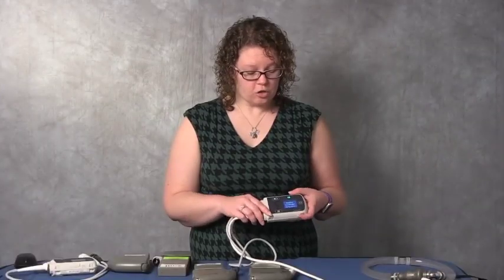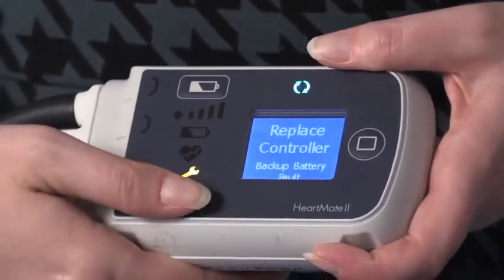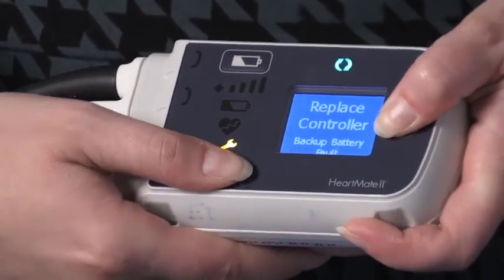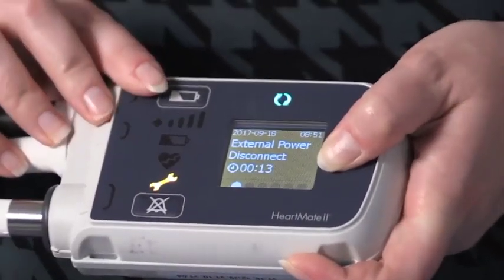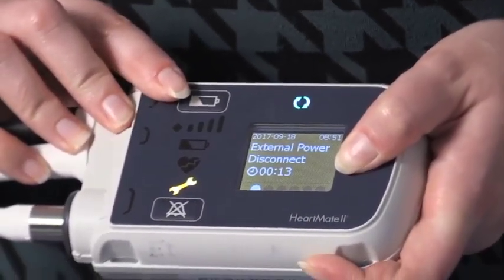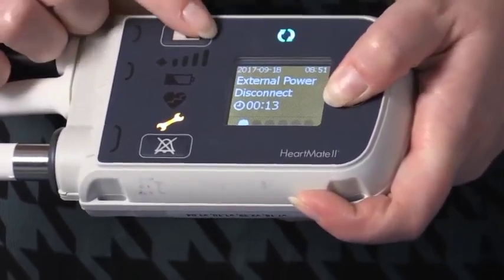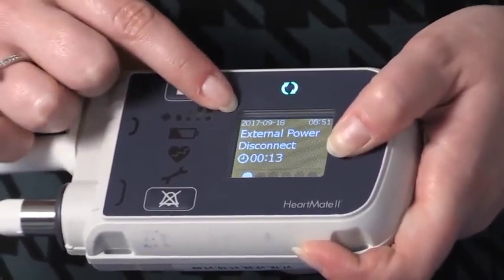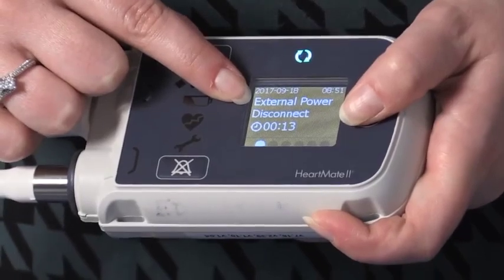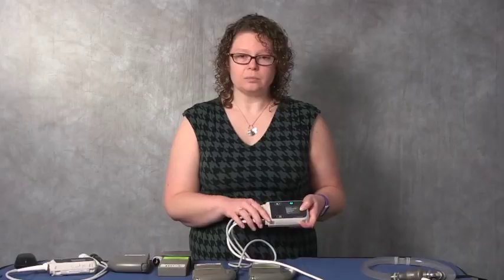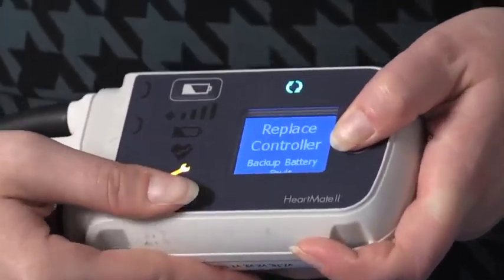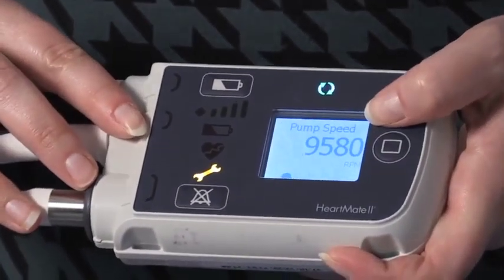Another feature of this controller is the alarm history menu, and you access that by pressing your silence button and your square button at the same time. And that pulls up the last 6 alarms that the patient had. As you can see, it date and time stamps the alarm. It tells you what the alarm was and how long it lasted. This is handy because patients will sometimes call and say, my controller alarmed, but by the time I got it out, the alarm had stopped. And so that lets us see what the alarm was that the patient was hearing.